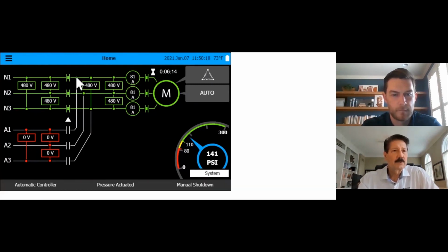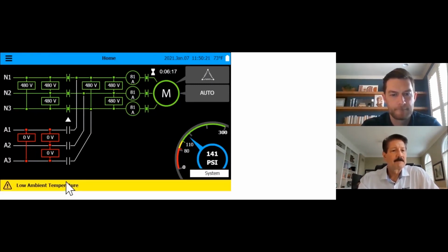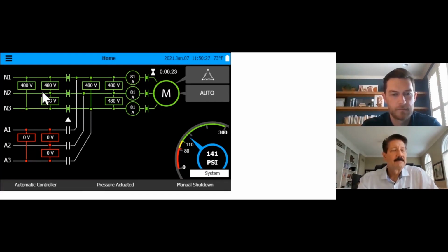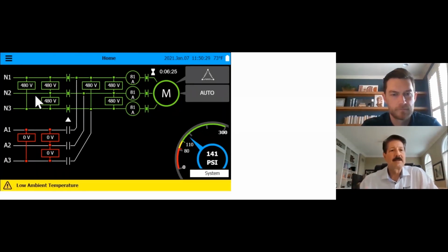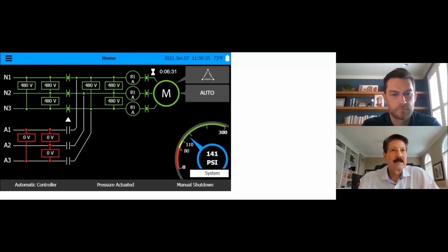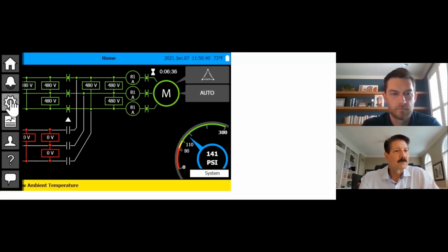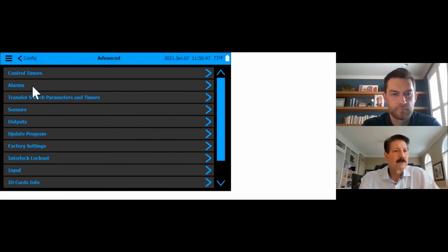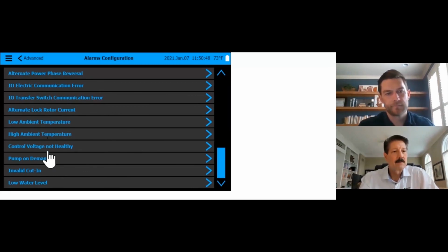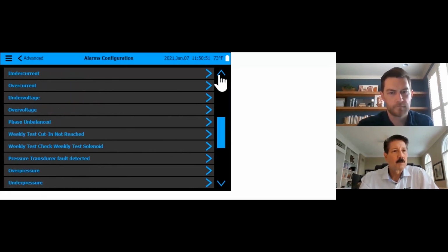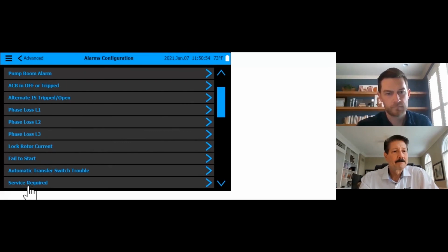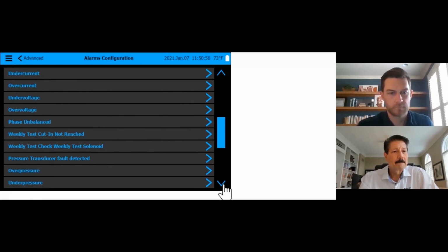So the alarms, red is critical, yellow is secondary, and again, that's what you're looking at. Normally, if you have a phase loss, well, you lost power, it's going to be red, and then you'll have a variation, I'll say phase variation, voltage variation, that'll be yellow. And really what happens here is that you want to focus on ones that are red, but the alarms, there's like 18, 19 alarms, and they will ultimately all show up on the screen if necessary. Let me just get back here.